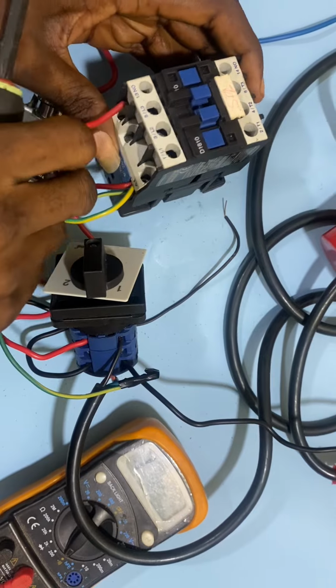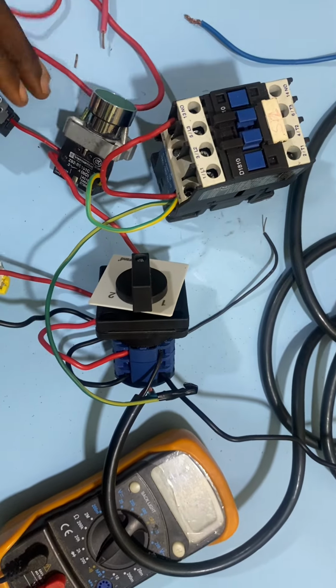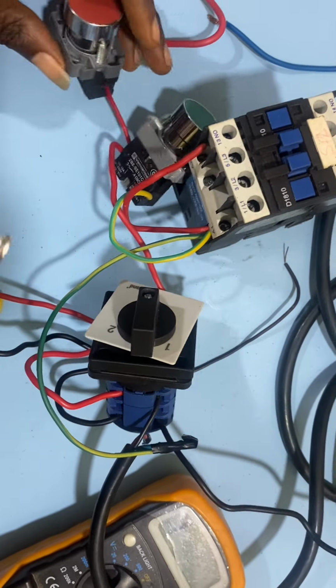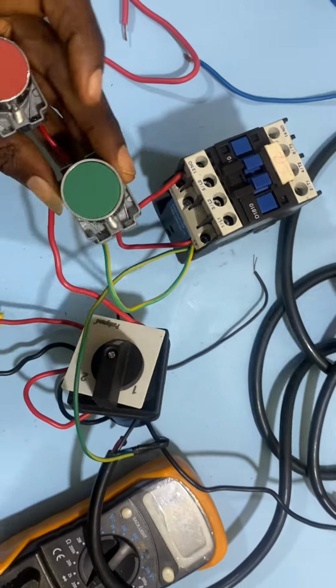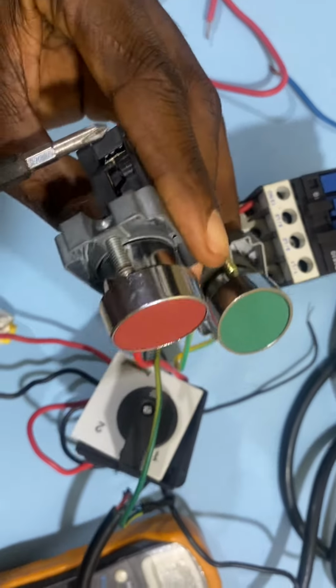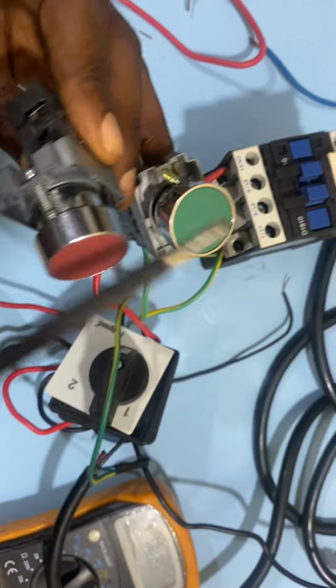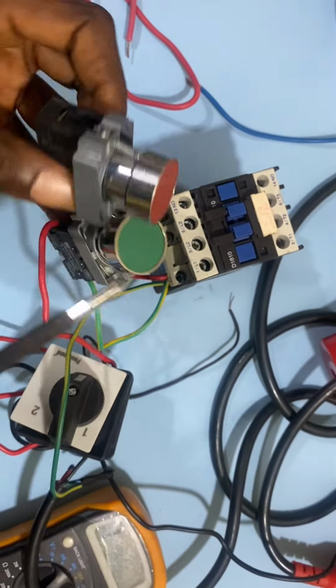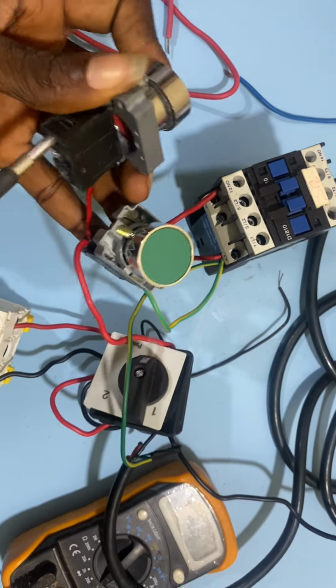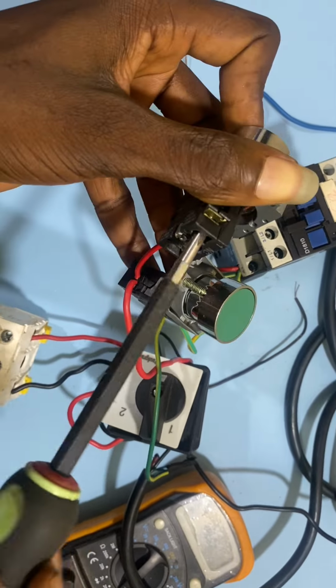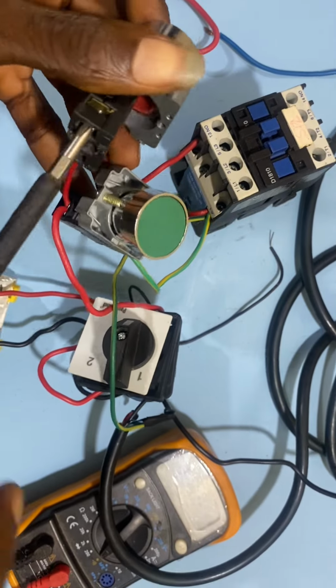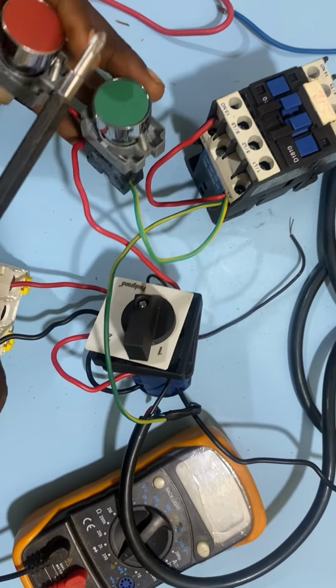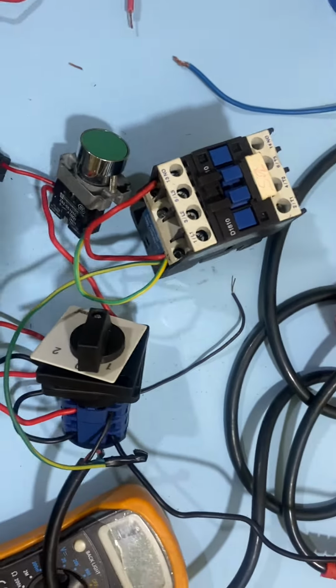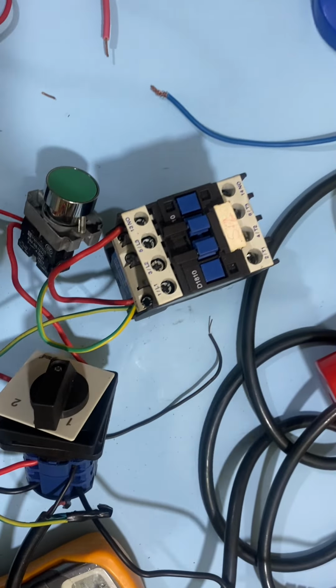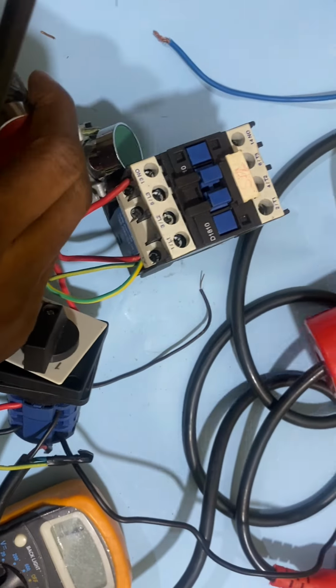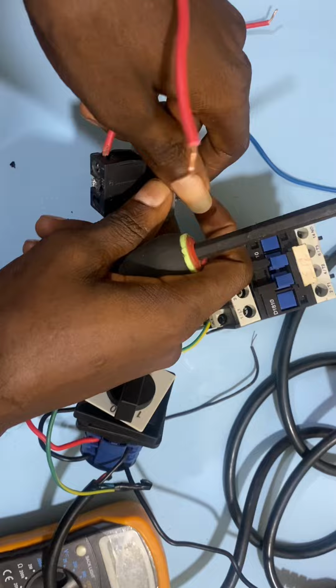Alright, so to create that same holding contact for the stop button of the contactor, I'm going to loop from this other side of the stop button of the contactor to the normally open contact, also of the contactor. So I select it. That is my terminal 2 of the stop button. So this is the cable that I want to use in that looping. That is my terminal 2.